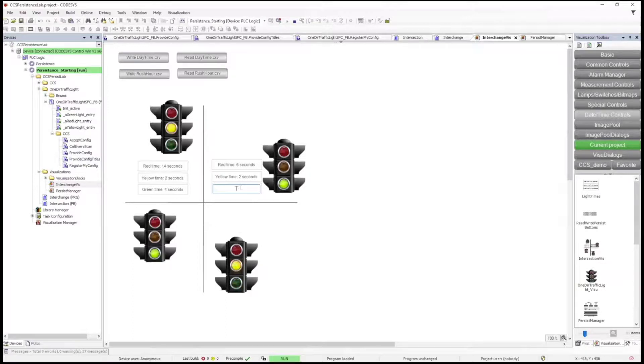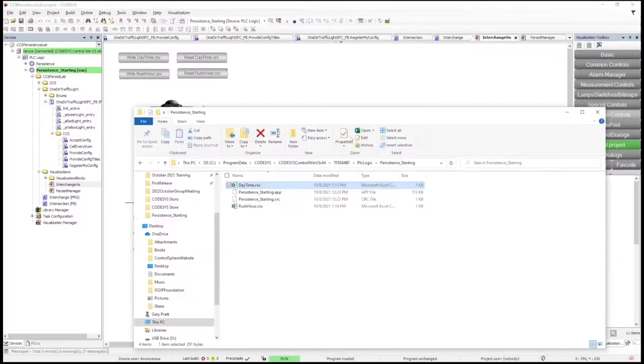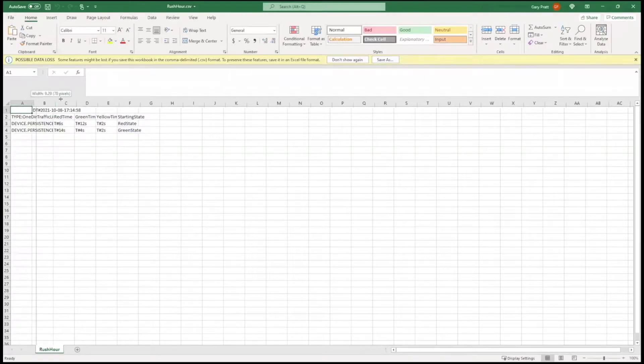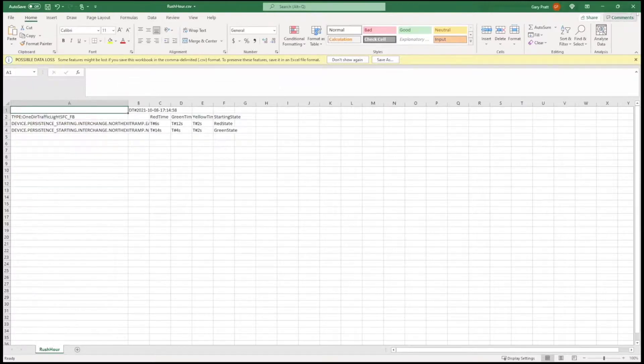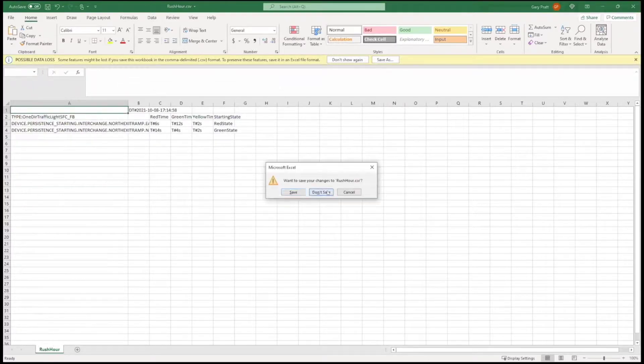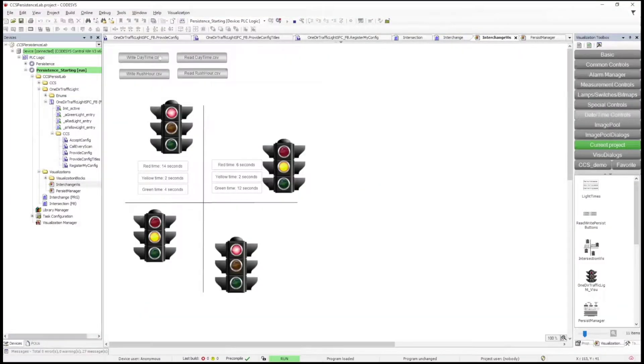So I've got these — now I'm going to write a rush hour file with these new parameters. You'll notice this thing is not behaving right because I've changed things out of sequence. But now we go back and look — we'll see we now have a rush hour file, and the rush hour has these new values in it that I just changed. We can come back in and read the daytime file or read the rush hour file. Notice they've changed and they resynchronize themselves.